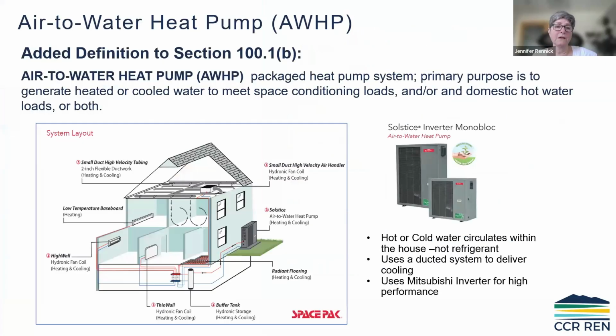and they use CO2 as the refrigerant. So that's another bonus. The other definition, in a slightly different section of that code, not under the water heater section, is air to water heat pump. You might start to see some of these. Sometimes they're referred to as a monoblock. The outdoor unit can heat your space, cool your space, but also heat your water. It could do any one of those things or all of it together.